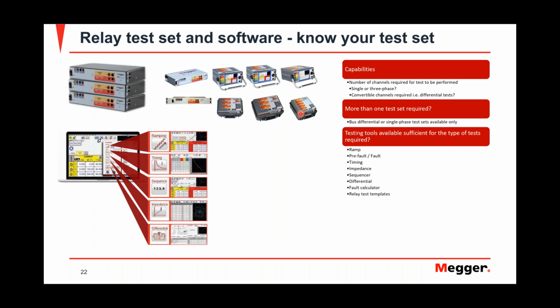Going into the software, knowing the testing tools that are available. Really all relay tester software has a certain set of tools, and by that I mean you're going to have a ramping tool where you ramp the voltage, the current, the phase, or the frequency, or all of them. How a fault test works. Timing tests, impedance tests, sequencers, differentials, fault calculators, relay test templates. Knowing all the different tools that the software provides you, and understanding, okay, if I'm testing this element, I think the best way to test this element would be with the sequencer tool or with the ramping tool. Knowing how the tools work and knowing how to apply them is something that will help you as you progress. So understand the relay software.